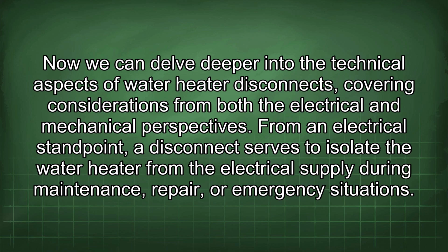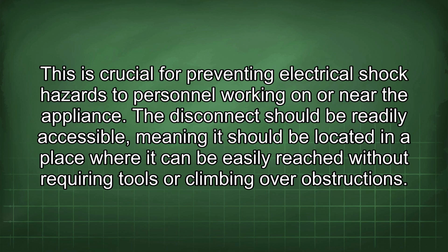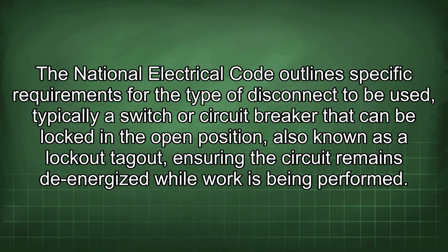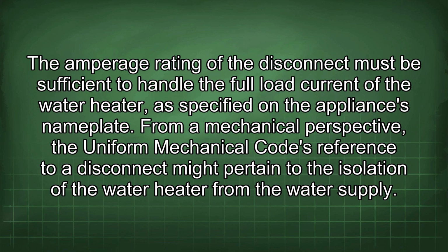From an electrical standpoint, a disconnect serves to isolate the water heater from the electrical supply during maintenance, repair, or emergency situations. This is crucial for preventing electrical shock hazards to personnel working on or near the appliance. The disconnect should be readily accessible, meaning it should be located in a place where it can be easily reached without requiring tools or climbing over obstructions. The National Electrical Code outlines specific requirements for the type of disconnect to be used, typically a switch or circuit breaker that can be locked in the open position, also known as lockout-tagout, ensuring the circuit remains de-energized while work is being performed. The amperage rating of the disconnect must be sufficient to handle the full load current of the water heater, as specified on the appliance's nameplate.